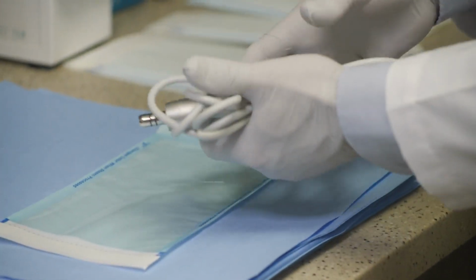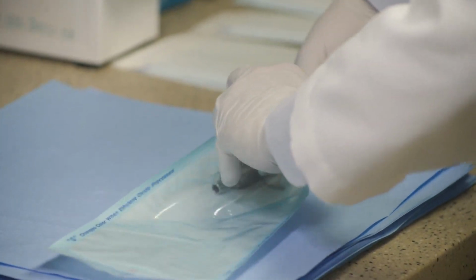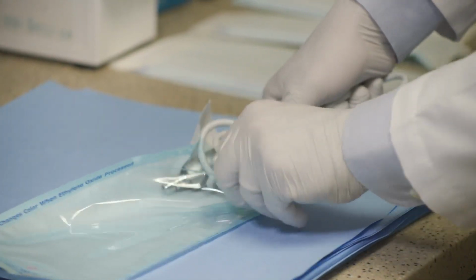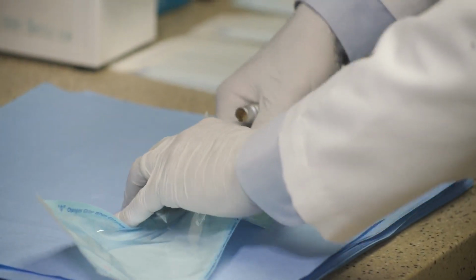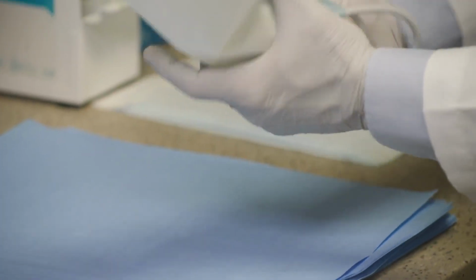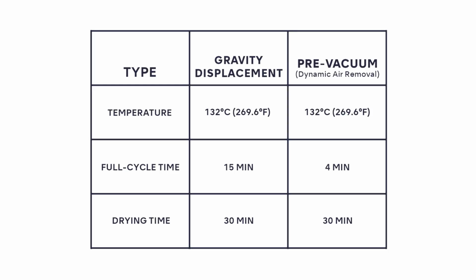Sterilization. Autoclave sterilization is recommended. Insert sterilizable components into a U.S. FDA-cleared sterilization pouch, compliant to ISO 11607-1. Seal the pouch. Use this chart for temperature and timing. Immediately after the sterilization cycle, remove the products from the autoclave and store in a clean, dry location.